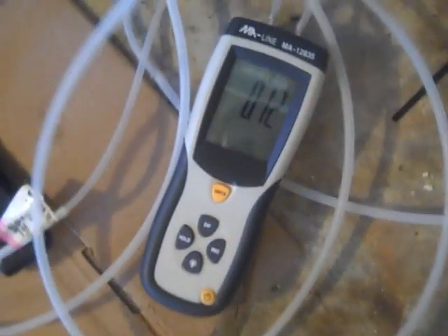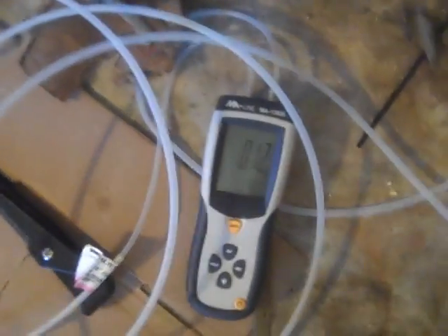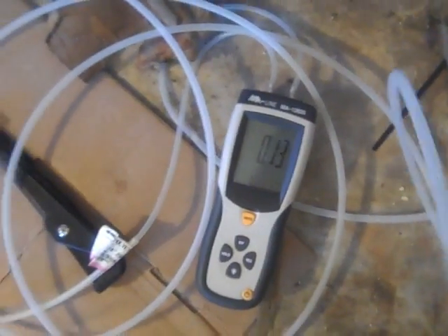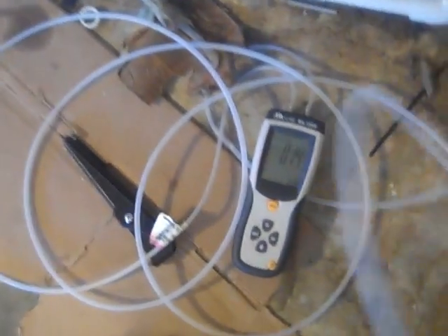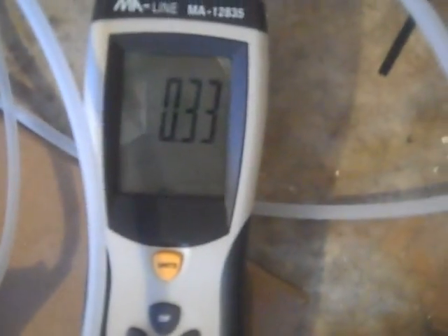Then we'll take the other end here. This is on low, this is just the fan G calling by itself. When this furnace does that, it runs on low speed. So we're going to start off with low speed. There's our return temperature. This is the Aprilaire 2200 air cleaner and we're just going to put that in there. We see here now we're on low and we have a pressure drop of .33.